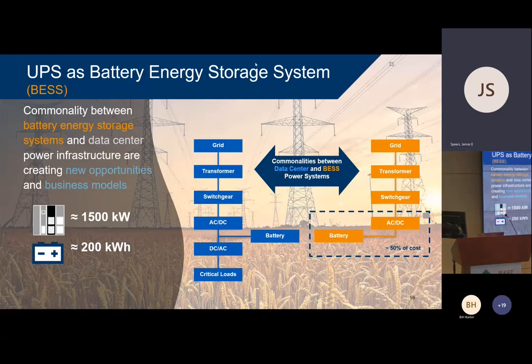Consider an energy storage system that some customers want to deploy on their site—they want a big battery with the ability to store energy for shaving peaks and similar uses. If this customer is a data center operator or critical power user, they either have a UPS or are contemplating one. On the left side of the slide, the blue blocks show a traditional UPS system: grid connection, transformer, switchgear, AC-to-DC rectifier, DC-to-AC inverter, the critical loads, and the battery connected to the DC link between the rectifier and inverter.